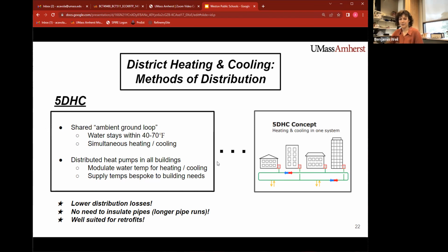And another possible configuration is this 5D heating and cooling system. So the way this works is it has this shared ambient ground loop. Water circulates through the geoexchange field, and it's distributed via the ambient ground loop. So the water in the loop is essentially the same temperature as the ground. And each building has an individual water-to-water heat pump to exchange heat between the ambient ground loop and the building supply water. And there's a single loop for both heating and cooling. Heat is extracted from the loop to satisfy heating loads or rejected into the loop to satisfy cooling loads.